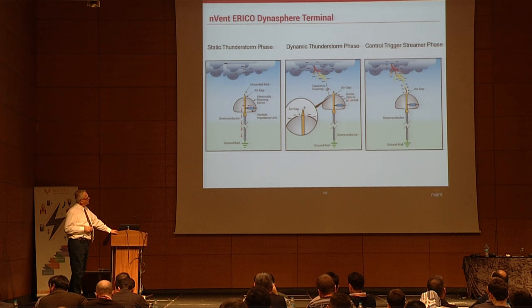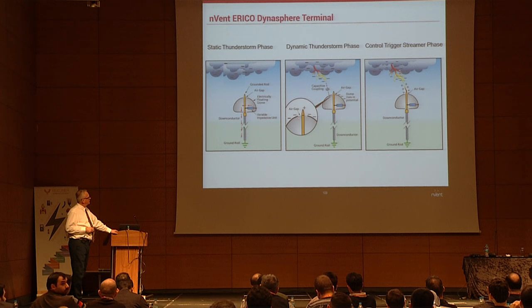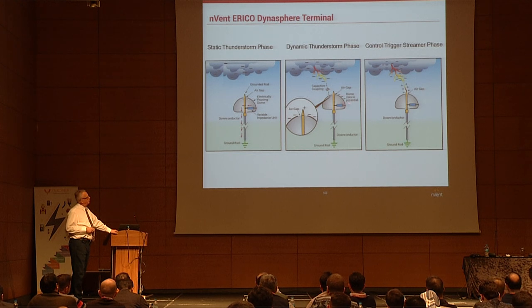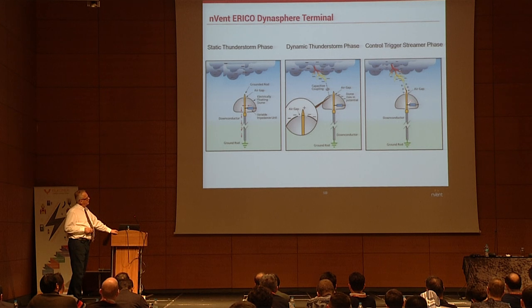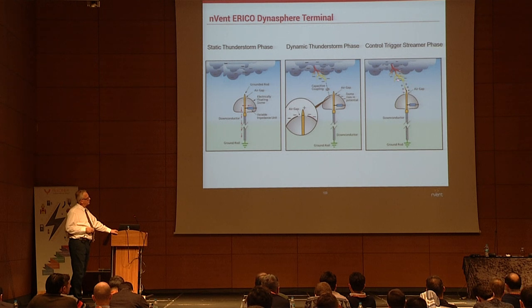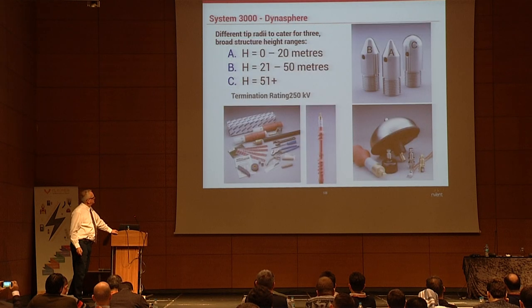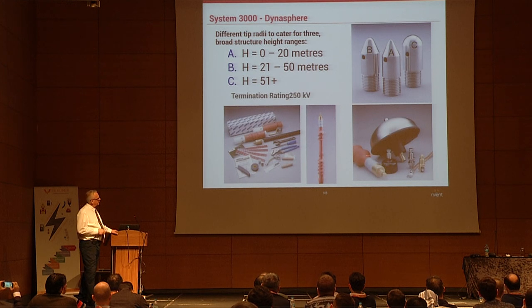When conditions are right, an avalanche event occurs — the charges are not able to bleed to earth but instead cross flash across the gap and send the upward leader. This is the controlled trigger streamer. The Dynasphere terminal has a different tip shape based on height, all part of the system, along with upper termination and other accessories.